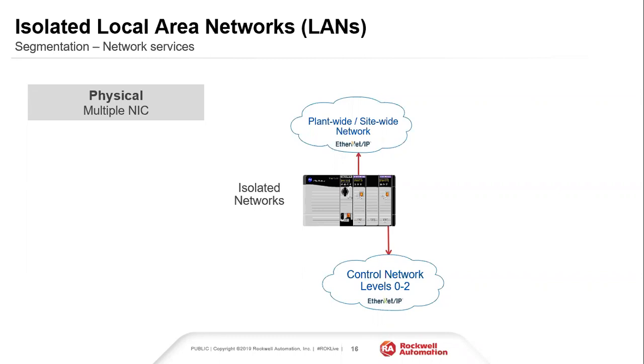I don't have to worry about how fast my historian is pulling. If I decide on my system that I'm going to add, let's say, 30 sections of MCC, whether it's low voltage or anything else, I could potentially just add another card and have that segregated out so it's on a completely different IP address stream. If I'm doing redundancy, realistically, all I'd end up doing is having 2 of these, chassis A, chassis B, and have the same segregation.